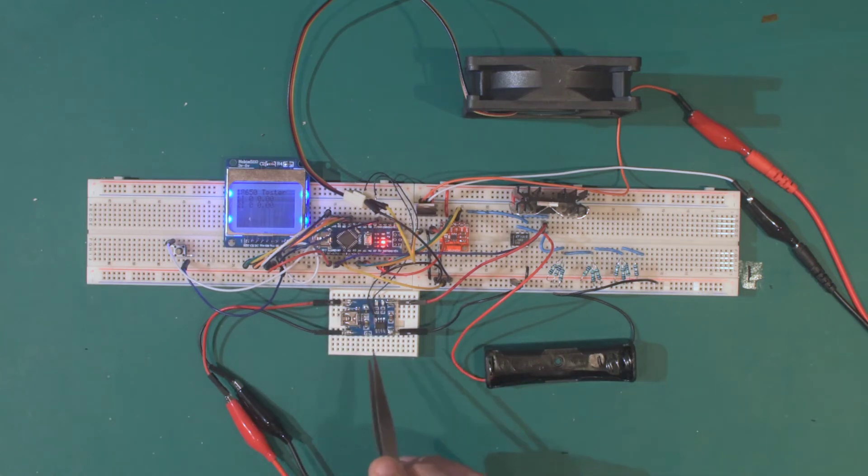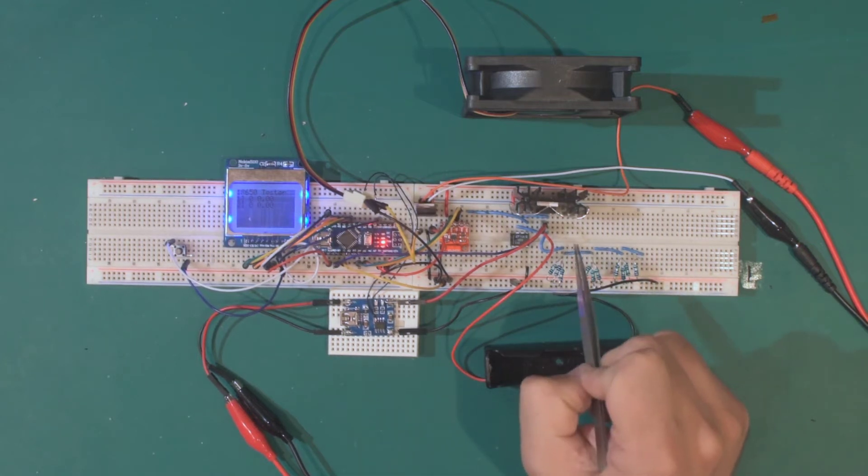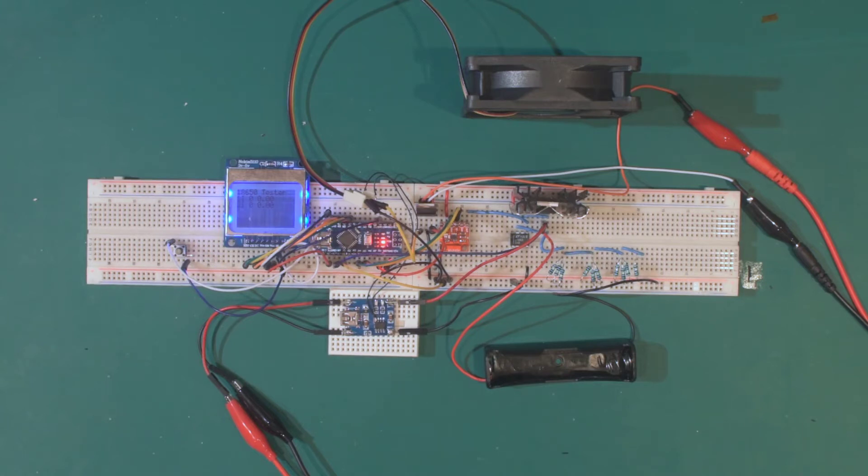When initiated, it will charge the battery before switching over to a constant current discharge and logging the capacity of the battery. As you can see, I've changed the display slightly. The display now shows an I for idle.